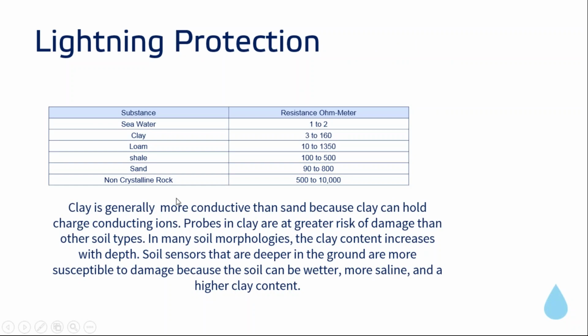And then we also mentioned the earth ground transient, or the lightning voltage surge that travels through the ground. Different geological media has different conductivities. Of course, seawater has a very low resistance, very high conductivity. Clay is a higher conductivity or lower resistance. Loams can vary depending on its clay content and salinity. And shale and sand is less conductive, and non-crystalline rock is a poor conductor.